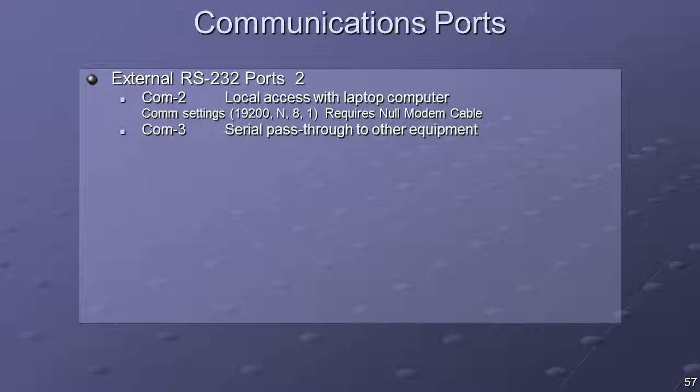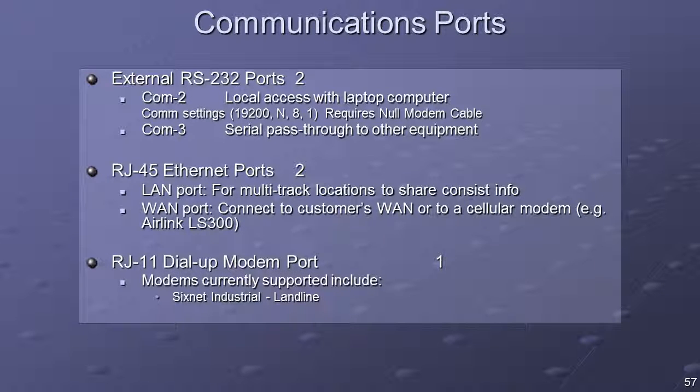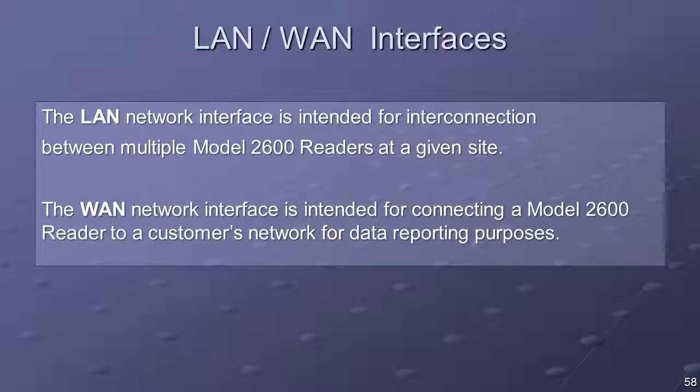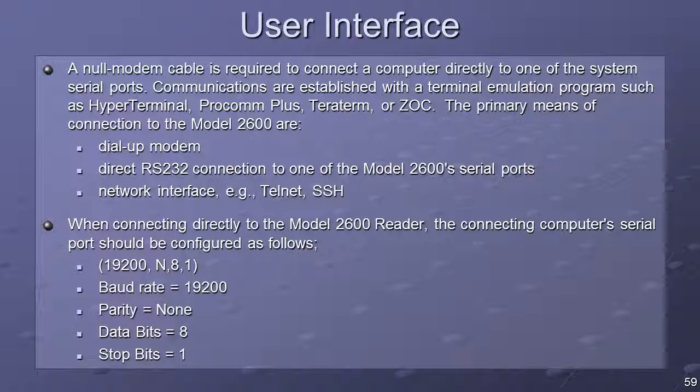Local access to the system menus is through serial port COM2. Remote access is possible through both the WAN network interface and through the RJ11 landline modem port. The LAN network interface is intended for interconnection between multiple Model 2600 readers at a given site. The WAN network interface is intended for connecting a Model 2600 reader to a customer's network for data reporting purposes. A null modem cable is required to connect a computer directly to one of the system's serial ports. Communications are established with a terminal emulation program such as Hyperterminal, Procomm Plus, Teraterm, or ZOC. The COM settings are 19200-N-8-1.